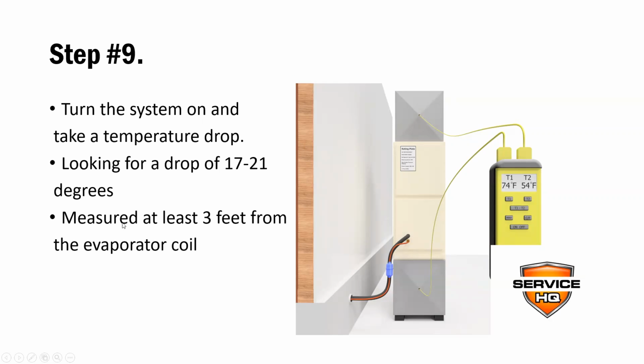So you have to make sure to measure this at least 3 feet from the evaporator coil. Here's our refrigerant line. So this would be our evaporator coil right here in this example. We have to make sure that this temperature probe is at least 3 feet away from that to get an accurate reading. Because if you're too close to it, it's going to throw your temperature off.